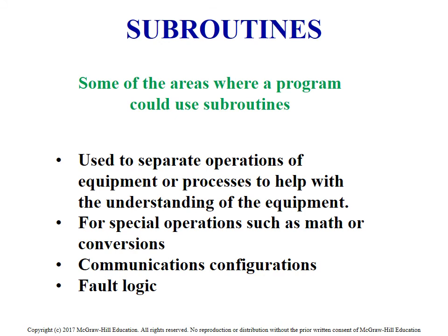And then very often you'll find that they'll separate the fault logic, the information that's getting passed on to touchscreens and emails and that kind of stuff. They'll have their own separate subroutine, allowing you to isolate all that information from the rest of it, so you're not ending up trying to find a fault in 10,000 rungs of logic. So it does help.